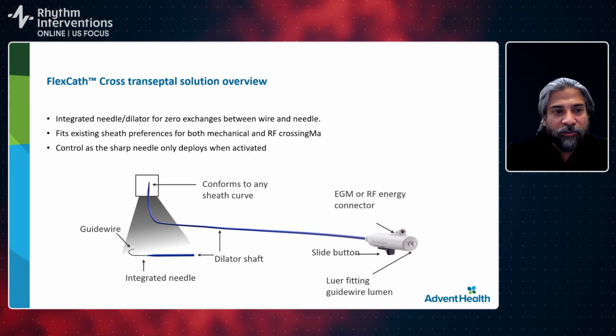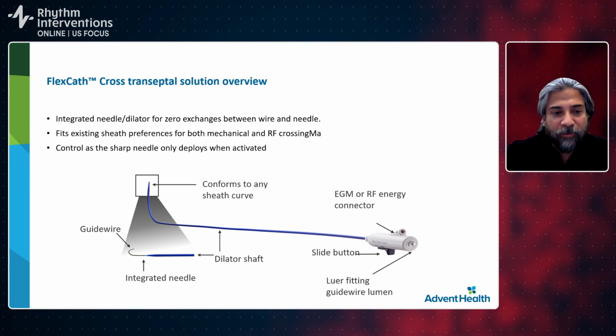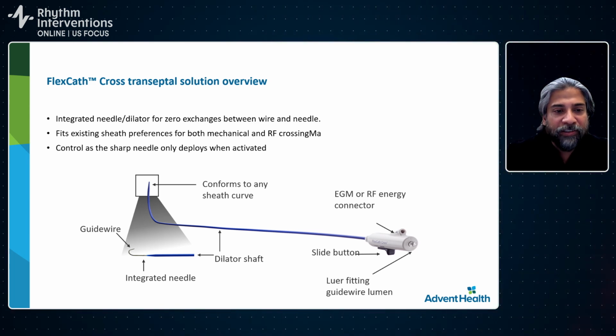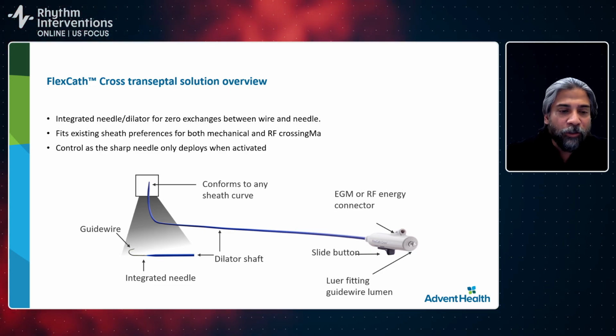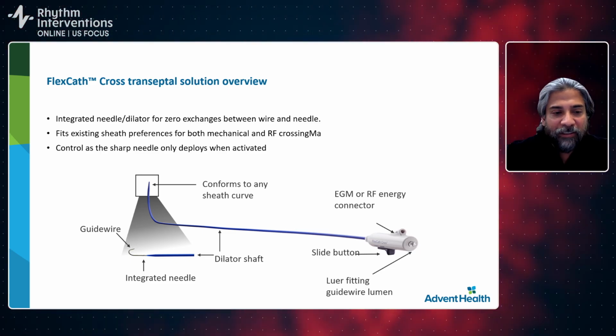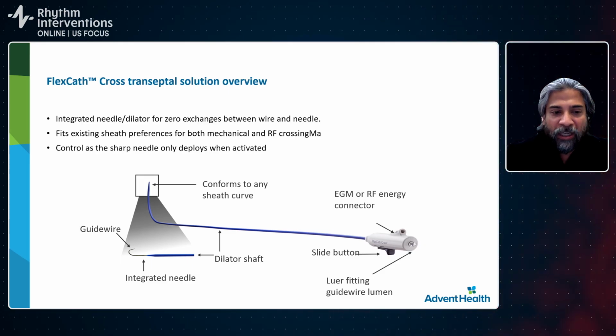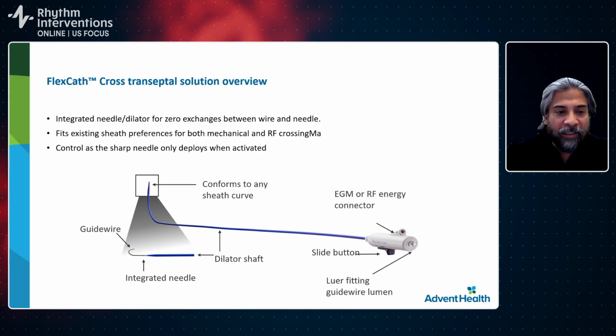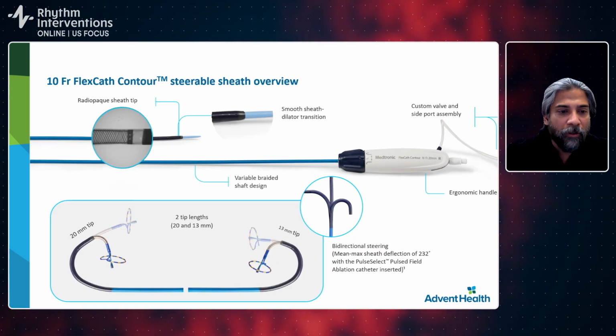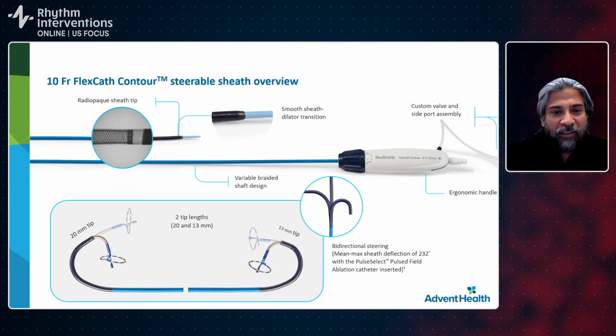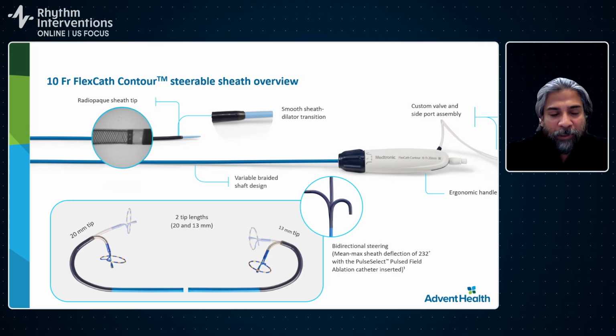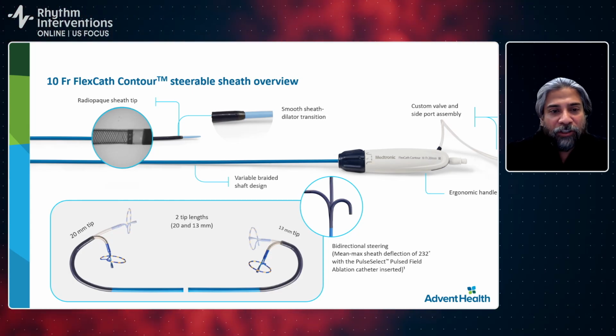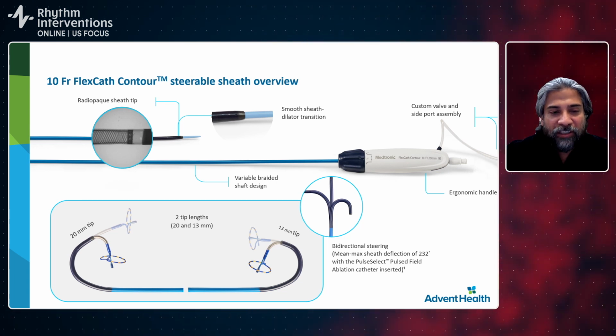The FlexCath cross transeptal system makes it a 0 exchange system. This dilator, needle, and wire system with RF capability is able to fit the sheath. It conforms to any sheath curve. And since the deflectable sheath is quite robust, we're able to deflect this to get inferior sticks as needed. And the sheath itself is becoming one of my favorite sheaths to go to, where it's a very smooth sheath dilator transition as you go transeptal across.